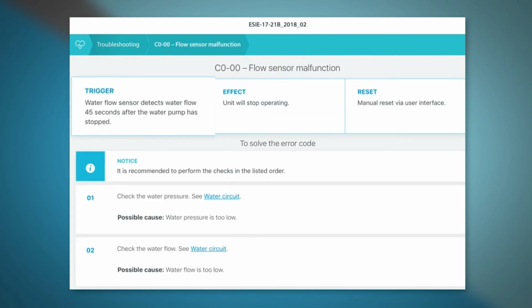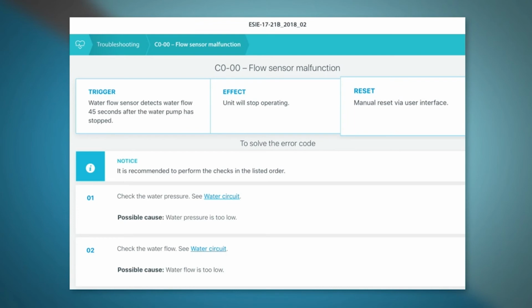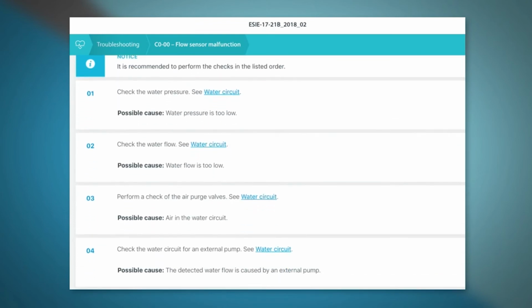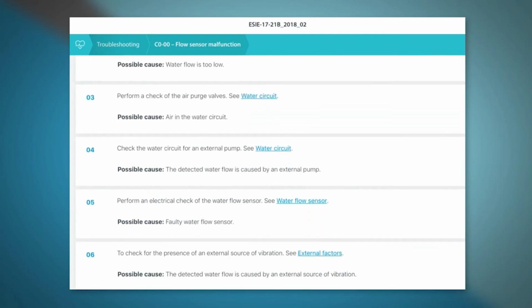We give you the trigger for each error code, the effect this will have on the unit, and how to reset the error code after you've found the root cause. eDoctor guides you in solving the error code by giving you a list of components to check in a recommended order. Let's check, for example, the water flow sensor.